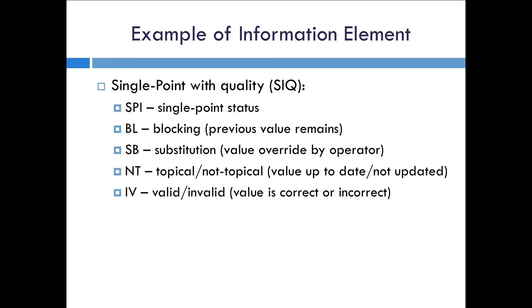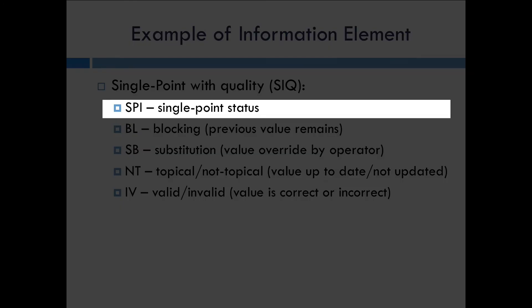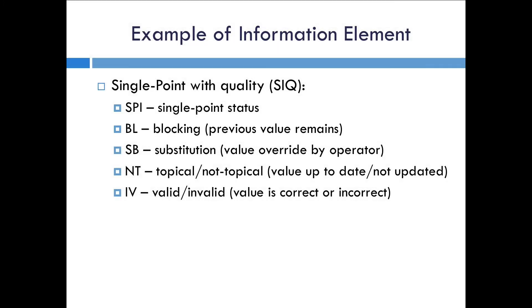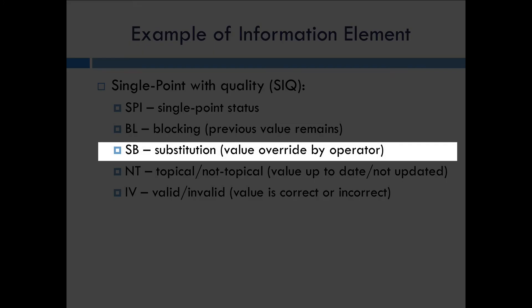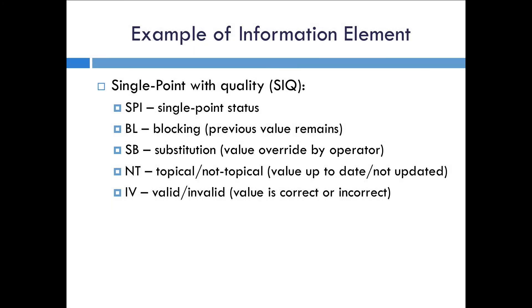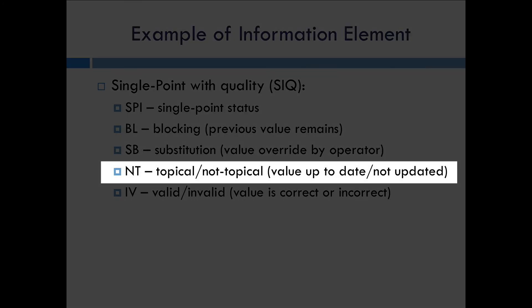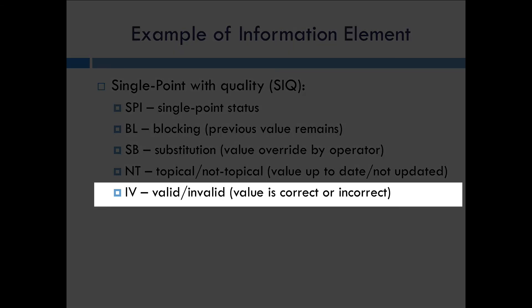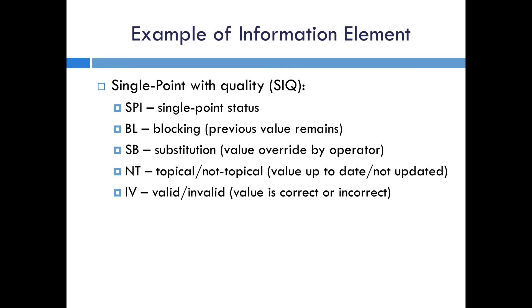A simple example of an information element is the single point with quality, which has five bits: a single point status bit, a bit for blocking so the previous value stays, a bit for substitution to override the value, a bit for topical or not topical to indicate whether the value has been updated — typically used in a data concentrator receiving data from downstream — and a valid or invalid quality bit. This is just one of the 40 different information elements.